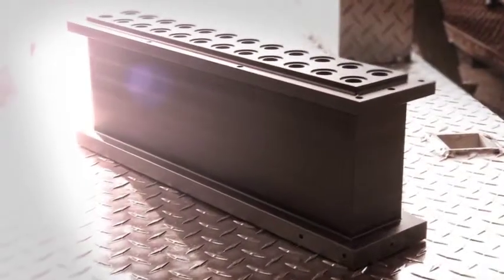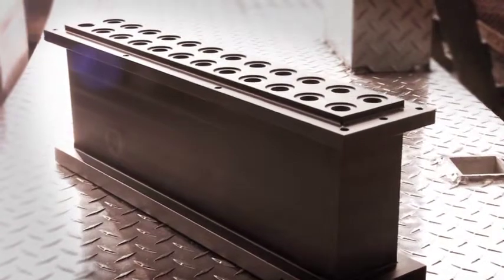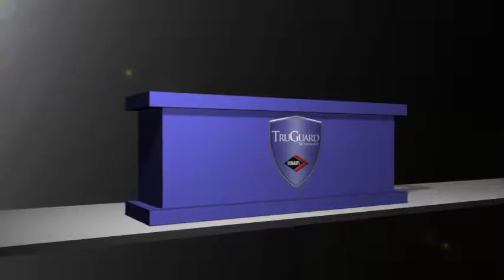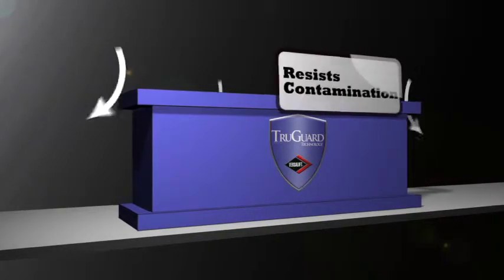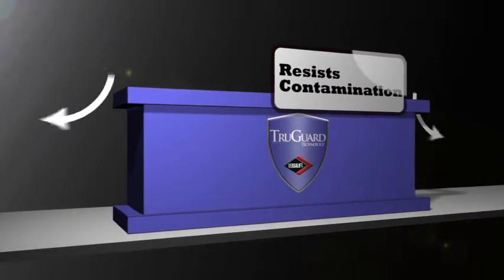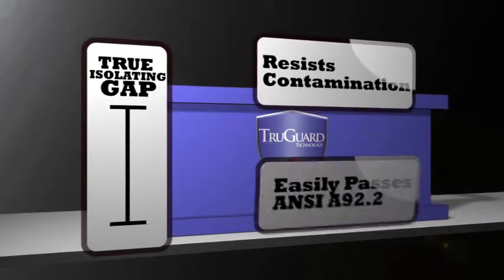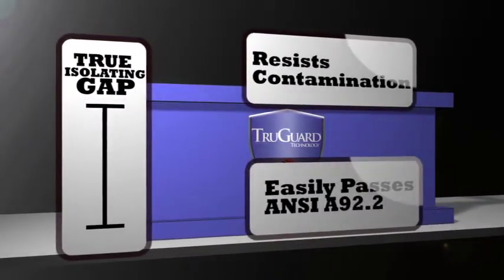TruGuard technology was developed and tested over several years. It's manufactured from a uniquely engineered polymer which gives its high dielectric properties and ultra-high strength. Single-handle plastic controls, when tested to ANSI A92.2, they barely pass that test. TruGuard's unique design and shape makes it resistant to contamination and it also gives it a true isolating gap so that it easily passes ANSI A92.2 test standards.